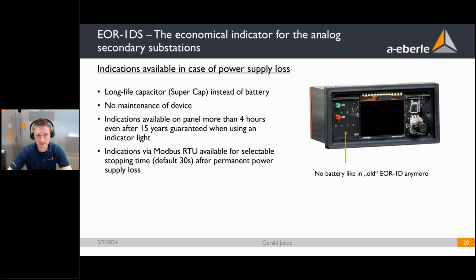The indication is available on the panel for at least 4 hours, and the 4 hours is really a worst case scenario that we calculated after 15 years of the device being installed, and in addition when you are using an additional indicator light. There are 3 different indicator lights available that you can wire to the device on the back and install somewhere outside of the secondary substation, so you don't have to open the door of the secondary substation and you directly see the direction of the fault or whether there is a fault at all. And even with using this indication light, we guarantee 4 hours of indication.